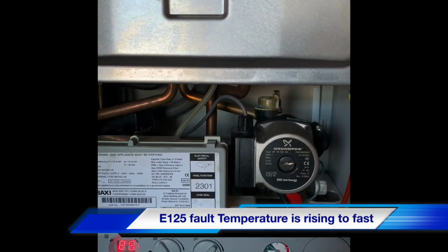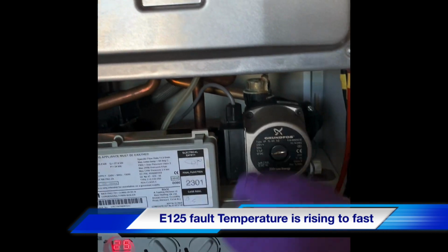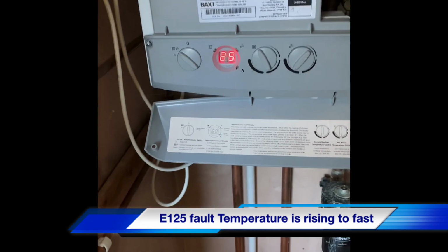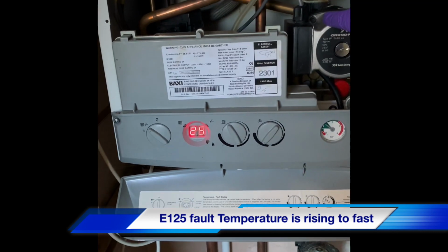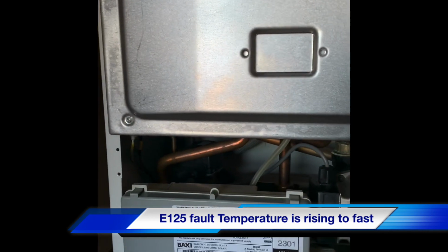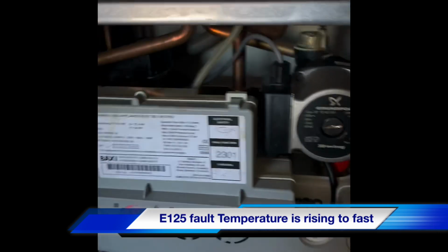So circulation problem, we'd be looking at pressure. Is there any pressure in the system? What's the water quality like? Does it do it on heating? Does it do it on hot water? Is the pump running? So let's just put a demand on for hot water, see what happens.